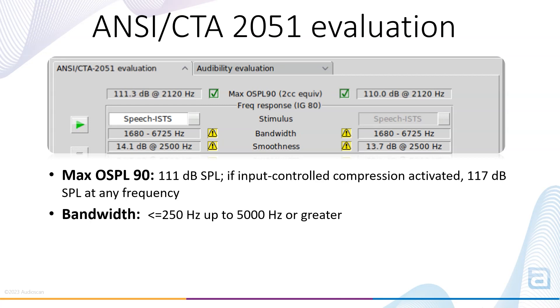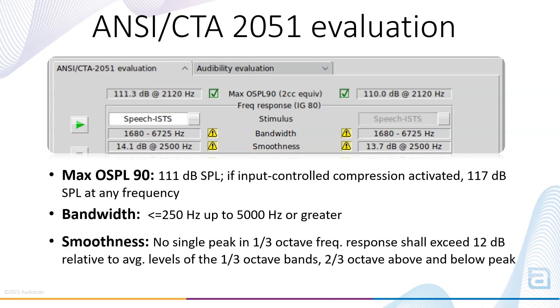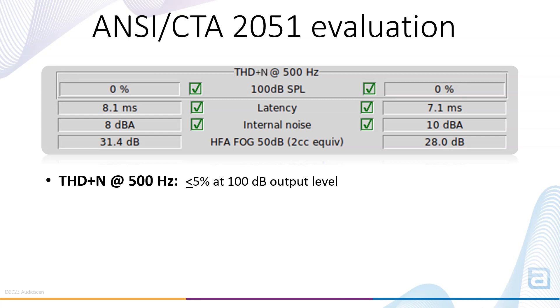Bandwidth measures the frequency response across important speech frequencies to ensure the hearing aid amplifies across an acceptable frequency range; the measurement can be performed with a swept tone or a speech signal. Smoothness measures consistency of frequency response across the frequency spectrum — no single peak in the 1/3 octave frequency response shall exceed 12 dB relative to the average levels of the 1/3 octave bands two-thirds octaves above and below the peak. THD plus N at 500 Hz is a measurement of unwanted hearing aid distortion and noise, measured at 100 dB SPL output level; the result must not exceed 5%.